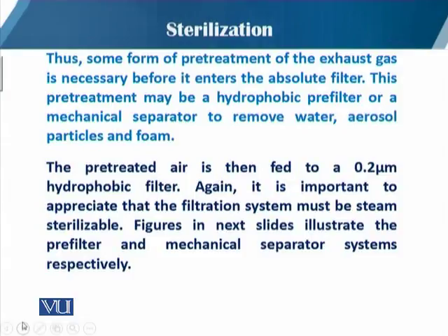Thus some pre-treatment of the exhaust gas is necessary before it enters the absolute filter. Because if we directly allow the exhaust air to pass through the filter, there is a chance of blockage due to the water vapors and the other media content carried in that air.